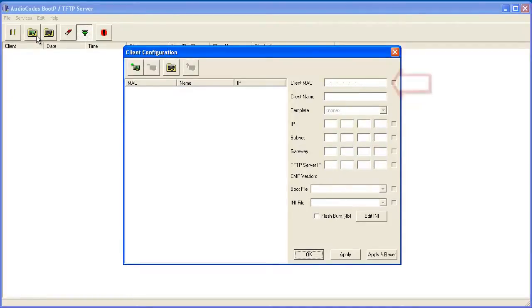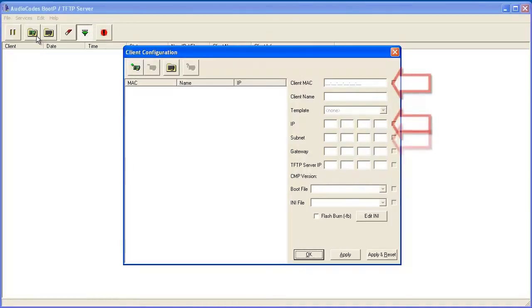The basic pieces of information are indicated in the Client Configuration window, accessed by clicking the Edit Clients button. Though there are many options, since we only need to assign an IP address, we will need the MAC address of the board to which the BootP utility will respond, as well as the IP address, subnet mask, and default gateway information.